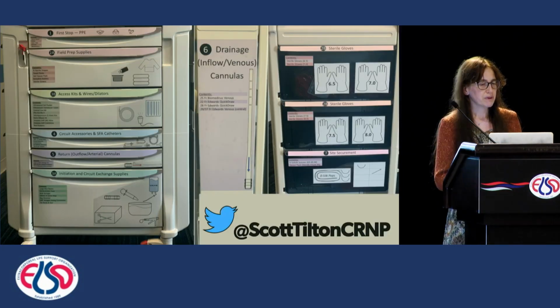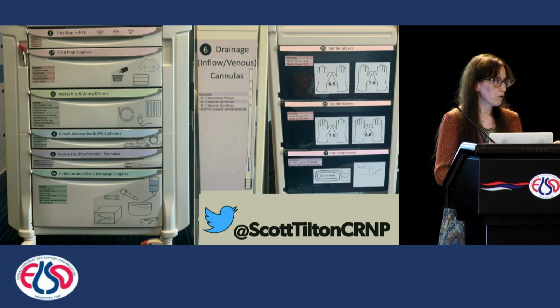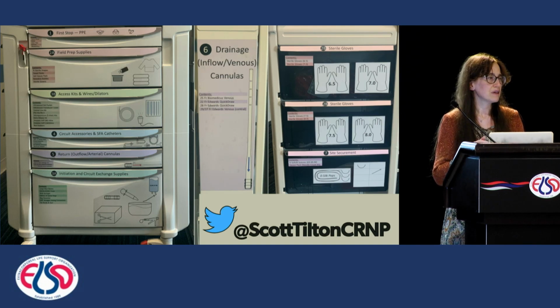Then you need to prepare your equipment. You should always have clamps available on your ECMO cart. You should have a hand crank if your centrifugal pump can be manually operated. Otherwise, you need a backup drive to manage pump failure. And you need a lot of stuff.